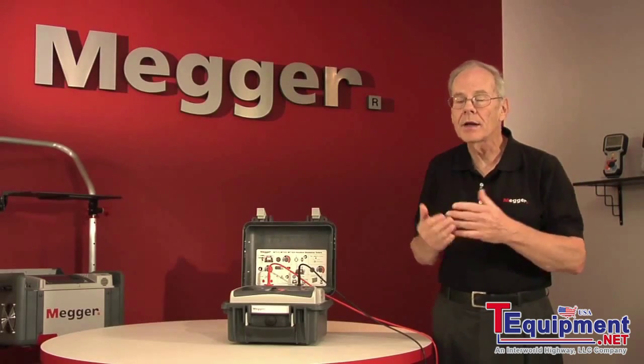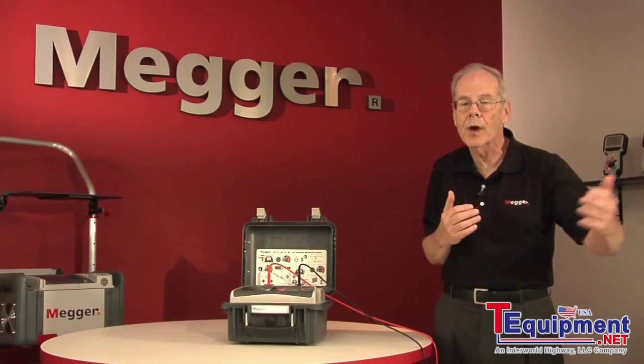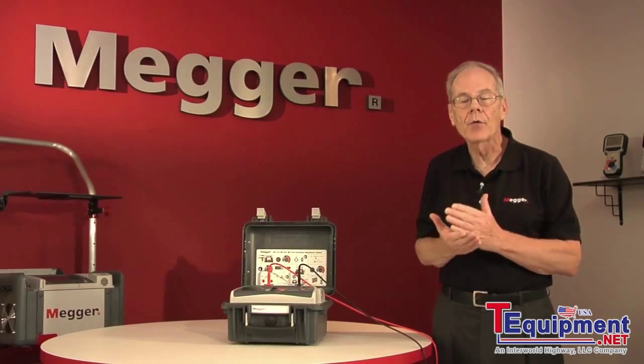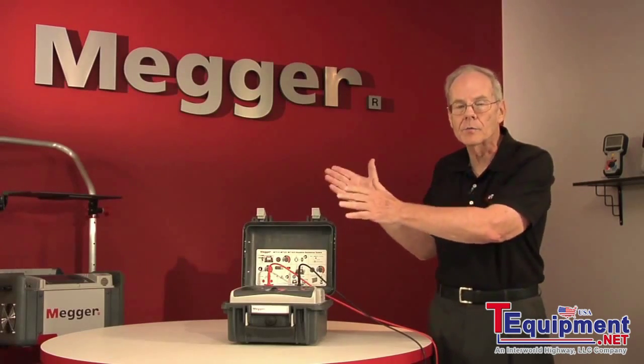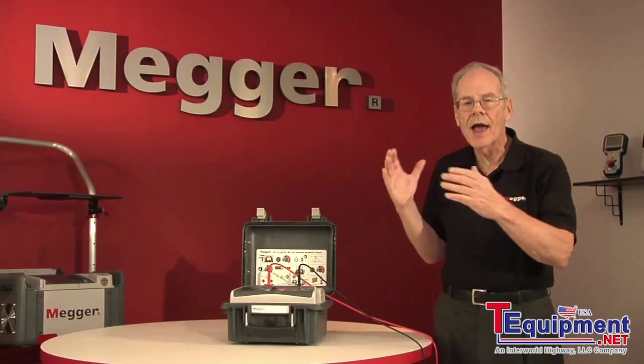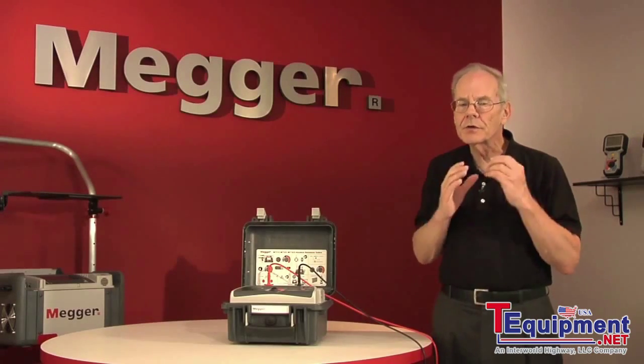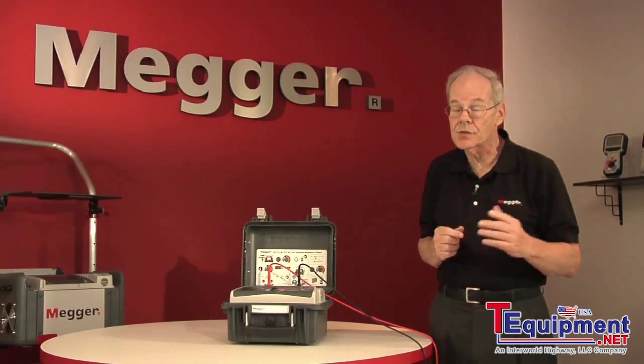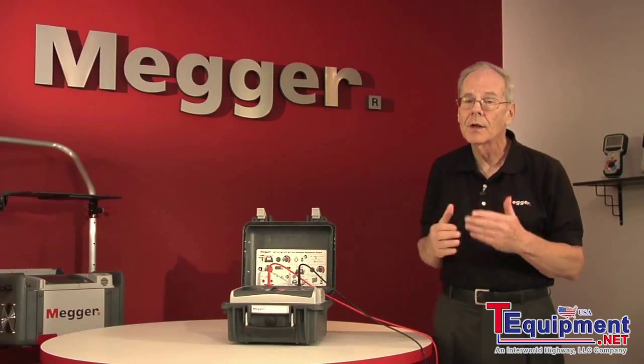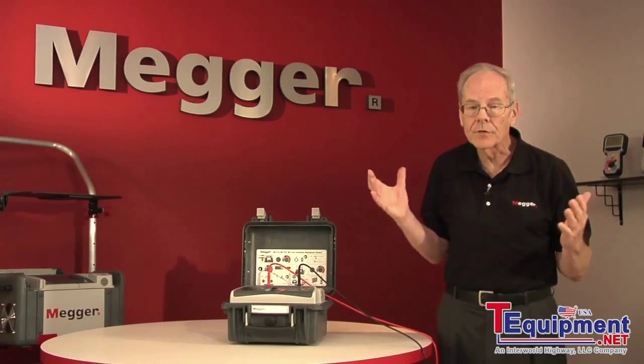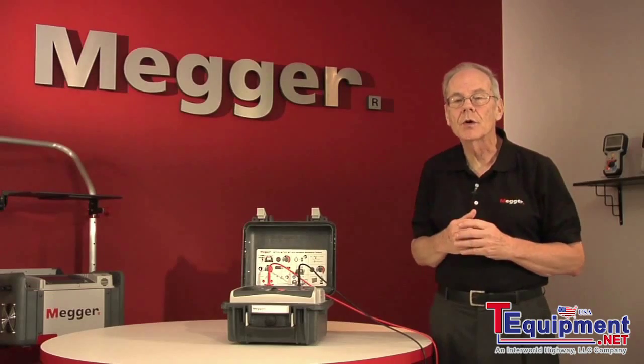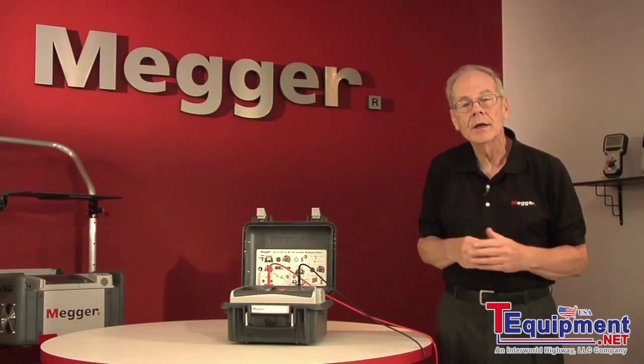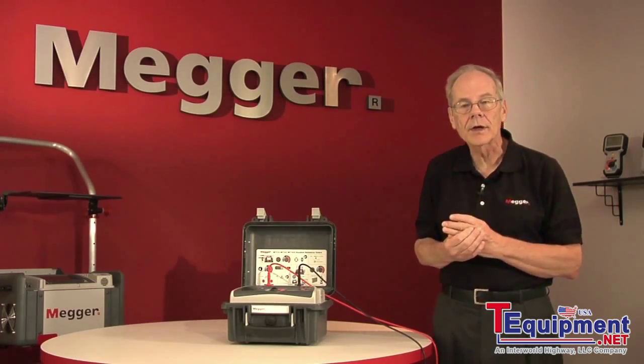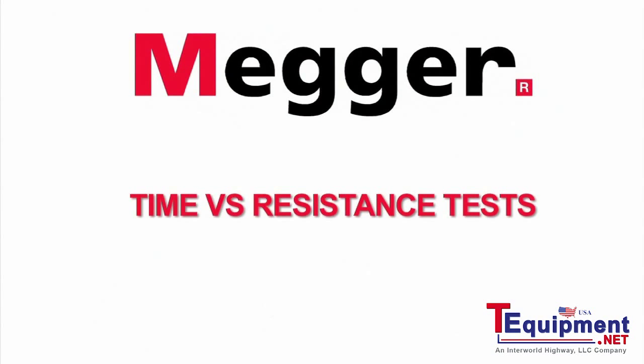This could be anything covering an enormous range. On good equipment, it can range from megohms to terohms. So the operator is now left with the task of interpreting what that number means. And if you have a previous test result, that's made a lot easier, but if you don't, it puts an onus on the operator. Consequently, the next two tests that we're going to look at are time versus resistance tests.